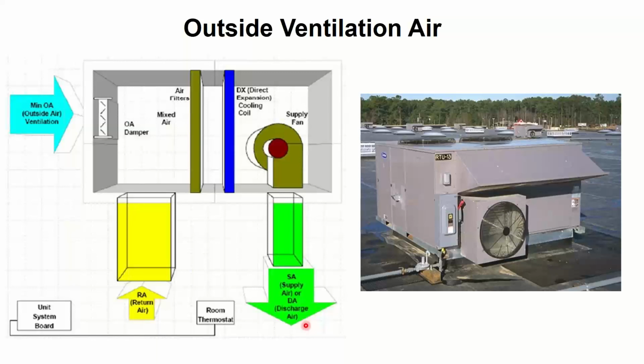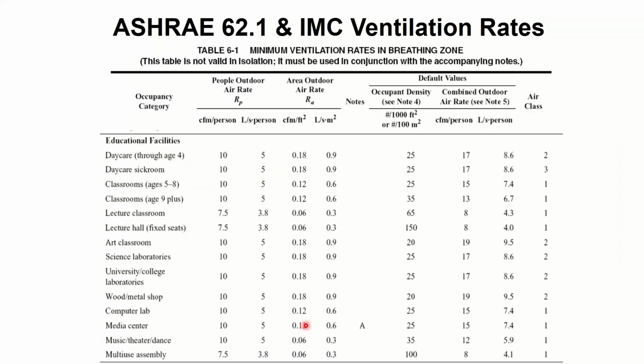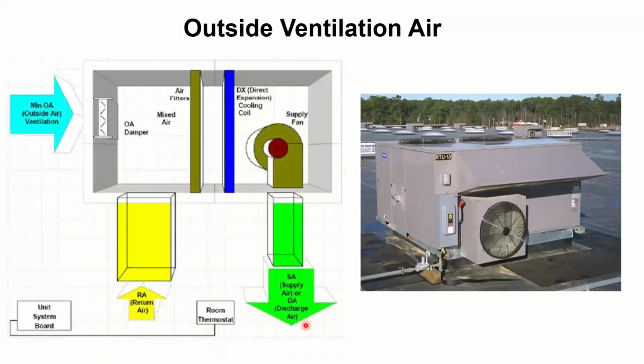In your existing buildings, we need to get your ventilation rates at least back up to code rates. Not doing the code required ventilation in general is a problem, and it's even worse with a disease situation like COVID-19. You may have seen recommendations, especially from May from CDC, getting their recommendations from ASHRAE, about bringing in even more ventilation, over-ventilating beyond the code required amount.